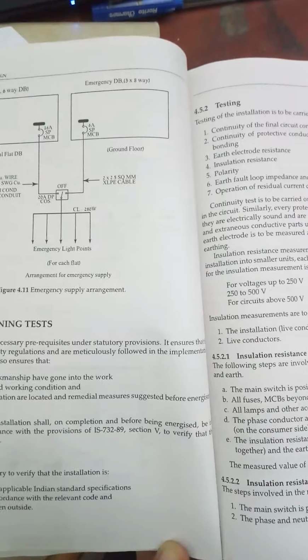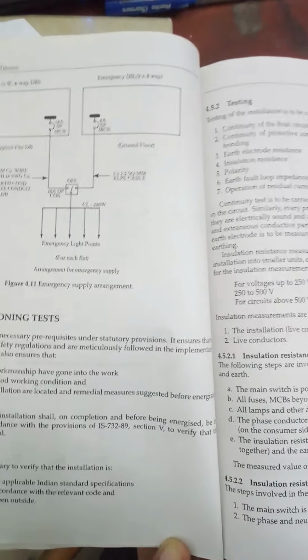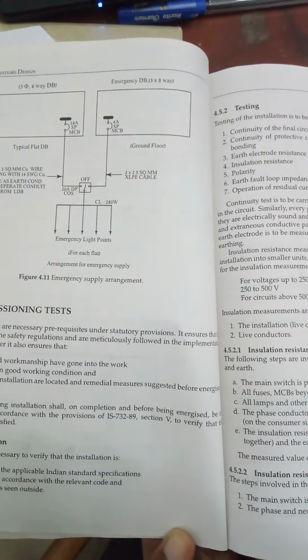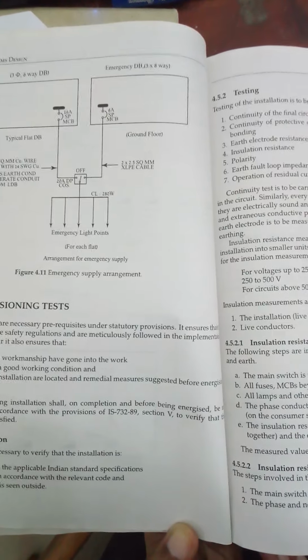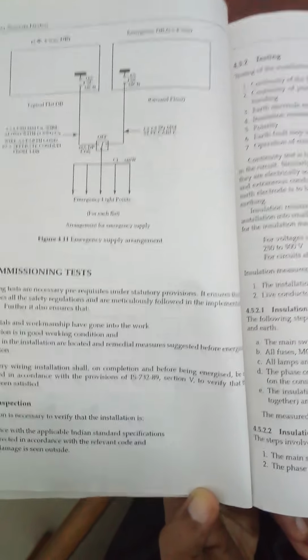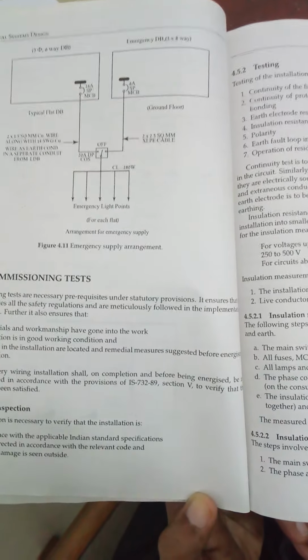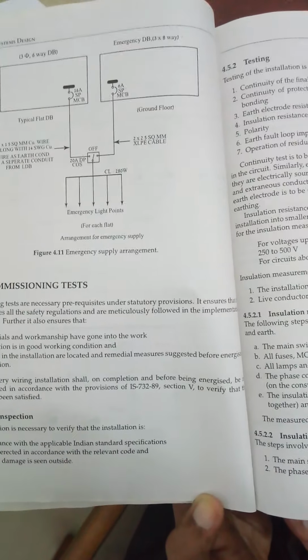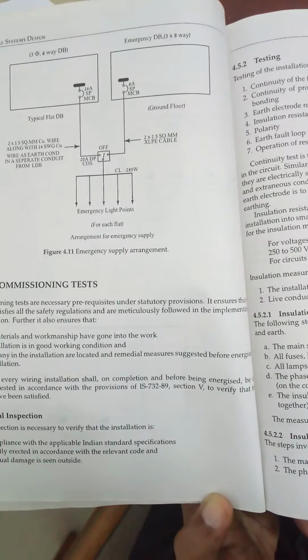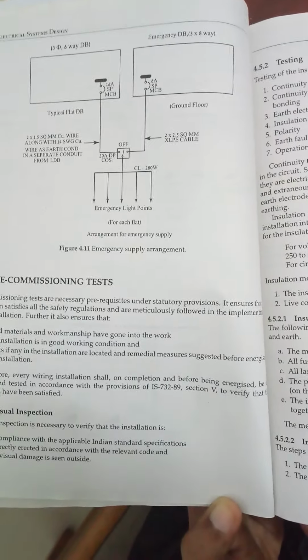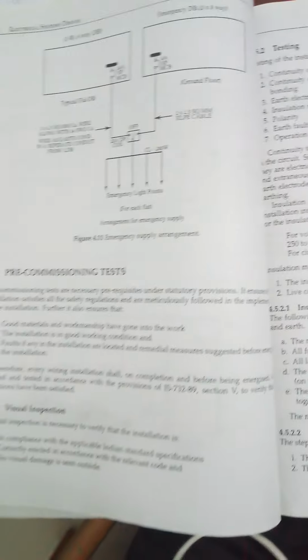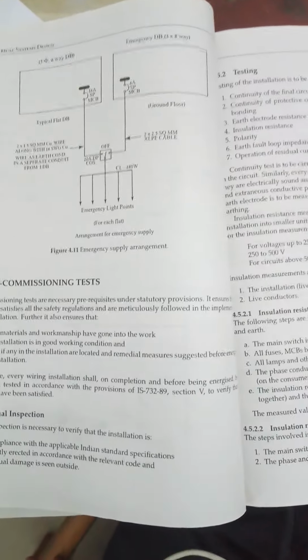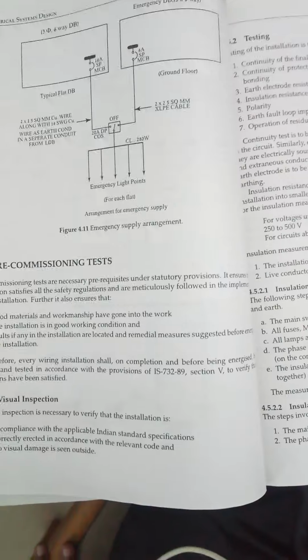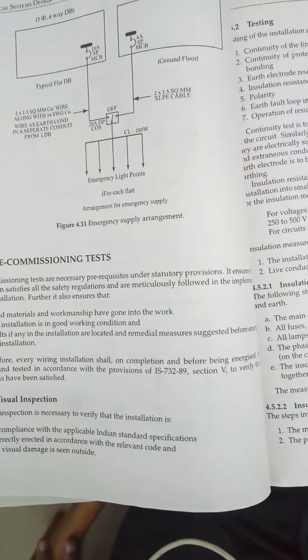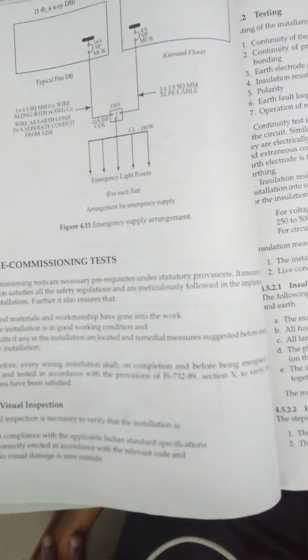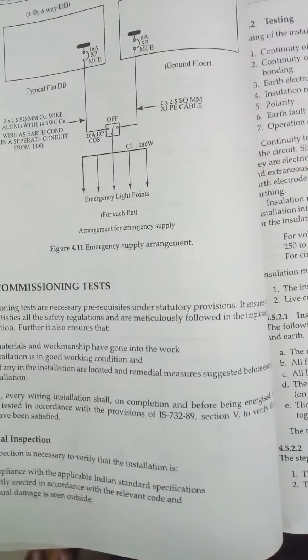Every wiring installation on completion and before energizing has to be inspected and tested as per IS 73289 section 5 and has to satisfy the requirement. First, visual inspection is done to verify the installation. It is applicable as per the Indian standard specification and correct. It will check whether it is done as per the Indian Electricity Rule or NEC, and whether it is correctly erected or not with the relevant code. And it also checks whether there is any visual damage, that is, which can be seen from outside.